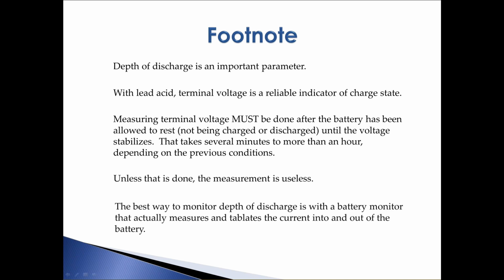So what you really want, if you have a battery system that can be fairly expensive, is to monitor depth of discharge with a battery monitor that measures and tabulates current into and out of the battery. It works by putting a shunt in series, usually with the negative lead to the battery system, measuring current going in when charging and coming out when discharging. That gives a very accurate measure of the battery's actual state of charge, helping you avoid hitting that magic 50% point. It's useful in lithium batteries, but essential in lead acid batteries.